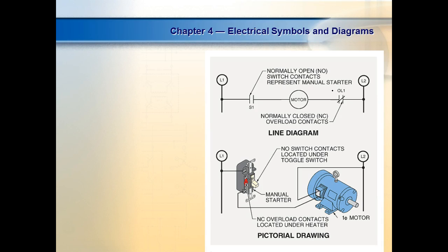Is that 1.8 amps when it runs or 1.8 amps when it starts? When it runs. That's the running. We call it the full load current. So that means if that was a 5 horsepower motor, it would be more than 5 amps. It would be like 10 amps over there. That is how much current that motor should pull if you're running it at its rated horsepower. When you start a motor, it's got a code on there, and we'll look at that later on, that tells you the multiplier to multiply the full load current to get the start current. The start current is always a lot more than the run current.